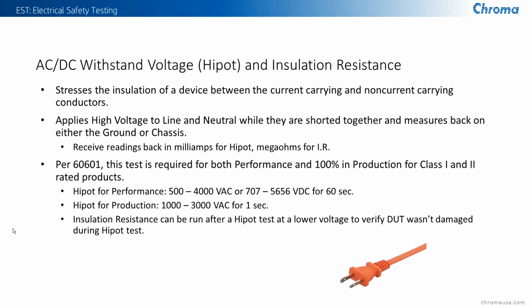We also do AC and DC high voltage withstand testing, which tests the insulation rating of the device. This is done by placing a high voltage between the line and neutral conductors shorted together on the input of the device, and then measuring that with respect to the ground or chassis of the unit. The leakage current is then measured to see if it is a substantial amount of current that could cause a shock hazard. There are various standards for this, but it gives you the ability to accurately measure that current and identify if it meets the low levels per each of the individual standards.